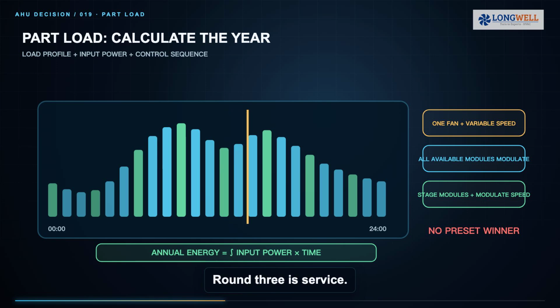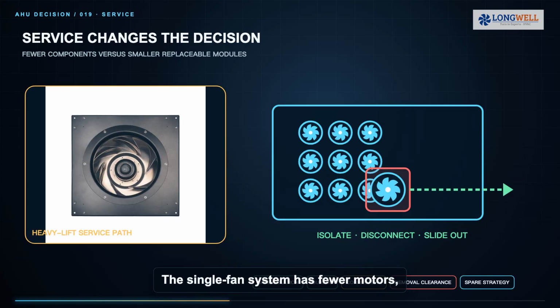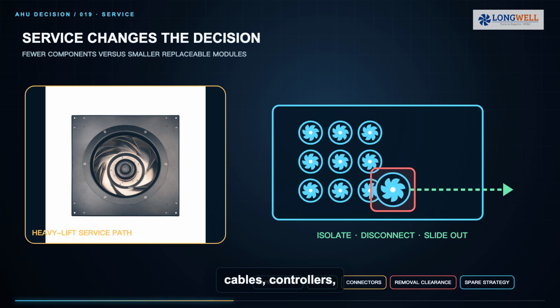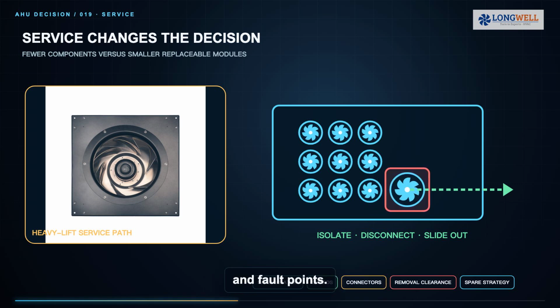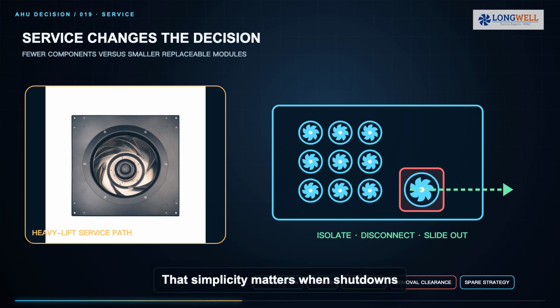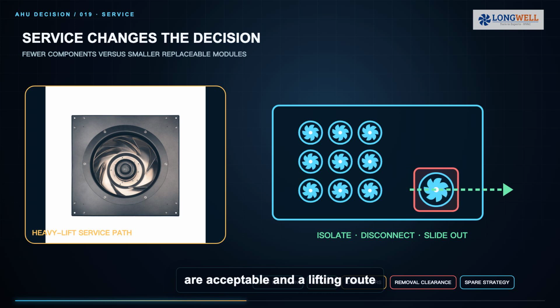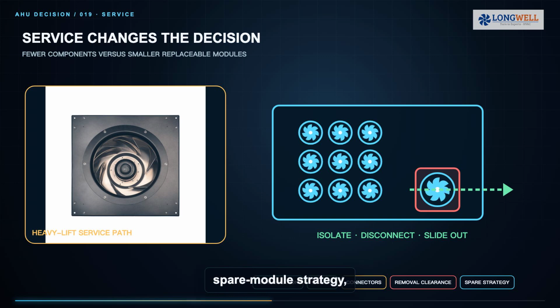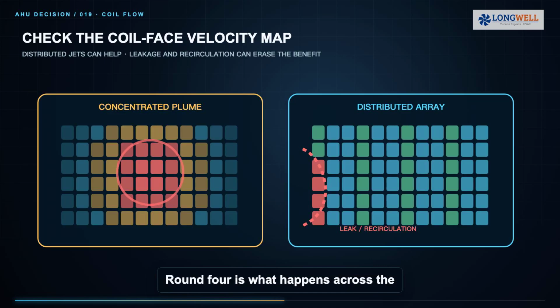Round 3 is service. The single fan system has fewer motors, cables, controllers, and fault points. That simplicity matters when shutdowns are acceptable and a lifting route is available. Fan wall modules are smaller and can be replaced one at a time, which helps where access doors are narrow or downtime is expensive. The advantage exists only with safe isolation, guards, connectors, spare module strategy, and enough clearance to remove a cell.